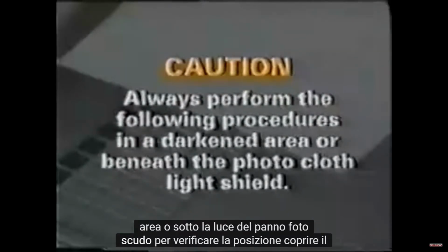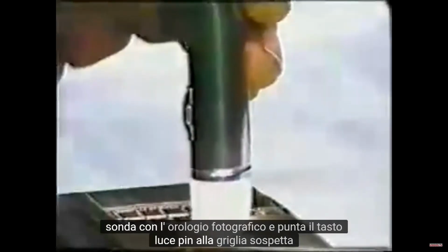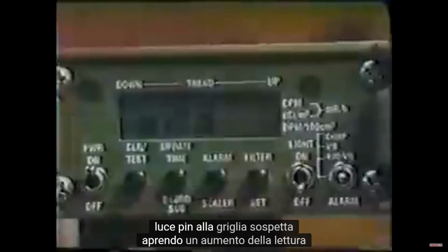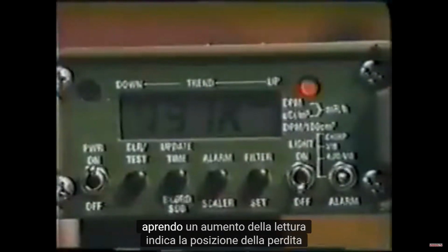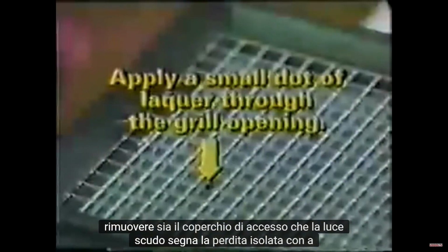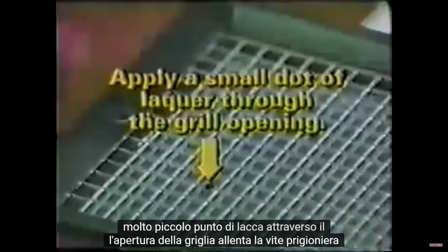Note grill opening location. Caution: to avoid damage, always perform the following procedures in a darkened area or beneath the photo cloth light shield. To verify the location, cover the probe with the photo cloth and point the pin light at the suspected grill opening. An increase in the reading indicates the location of the leak. Remove both access cover and light shield. Mark the isolated leak with a very small dot of lacquer through the grill opening. Loosen the captive screw and turn the probe face up and open the hinged cover. Exposing only the hinged cover, the Mylar window is ready for repair.